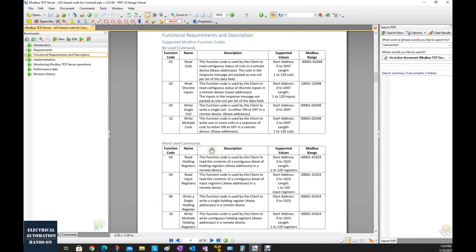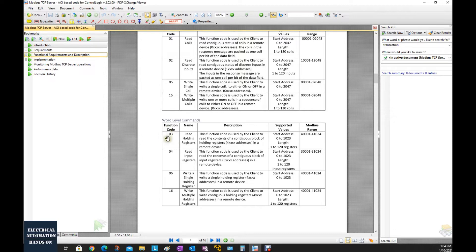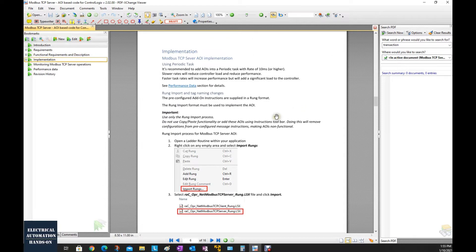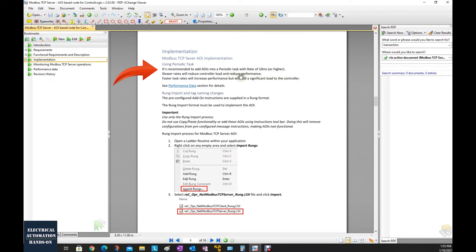The commonly used Modbus TCP function codes are 03 and 16. From the server side, we are waiting for the Modbus client to read or write data. In this test, I will use ModScan software running as a client to show how to send and read data from the client side. Also keep in mind: it is recommended to add this AOI into a periodic task with a rate of at least 10 milliseconds. In this video, I will show how to create a periodic task and implement this.